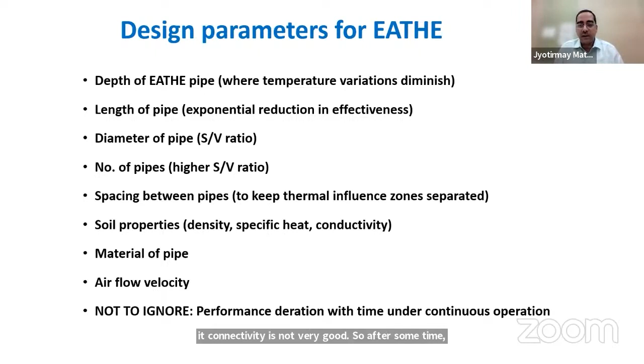Air velocity, as I said, is a very critical parameter because it governs your energy consumption. Not to ignore, if you are continuously operating an earth air tunnel, the performance would deteriorate over time. I repeat, if you are operating it continuously for 4, 5, 6 hours, because of the thermal resistance, the heat has crossed the pipe but is still in the soil. It has to go further, far from the pipe, and it takes time. It's a relatively slow process, especially if the soil conductivity is not very good. So after some time, there is a 20%, 30% deterioration in the cooling effect that you have initially, and that is to be taken care of in designing.